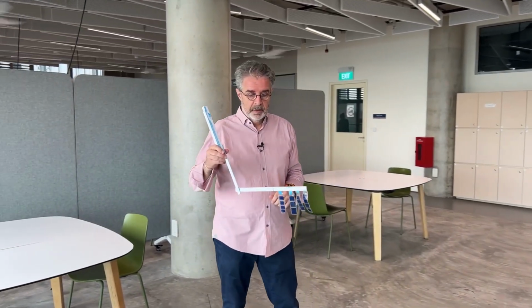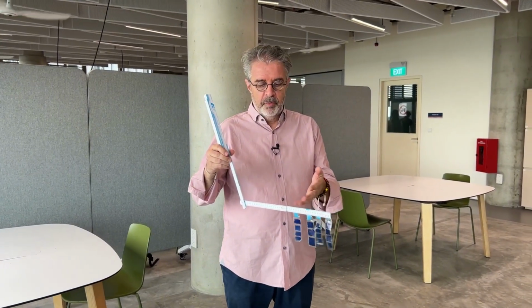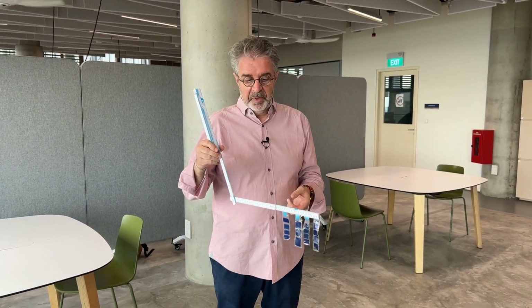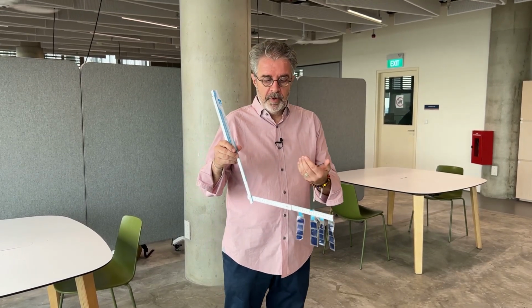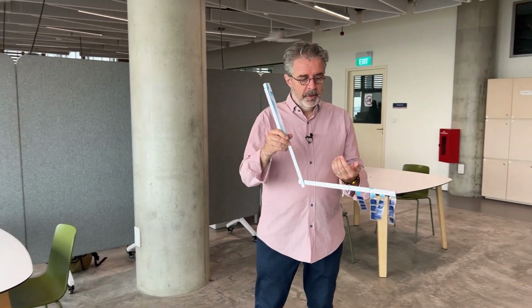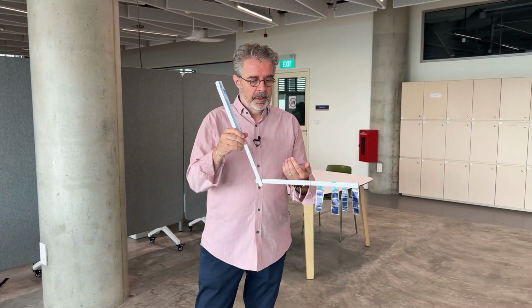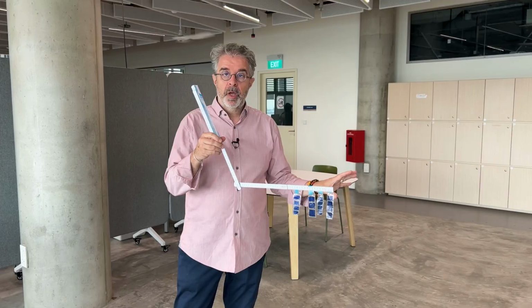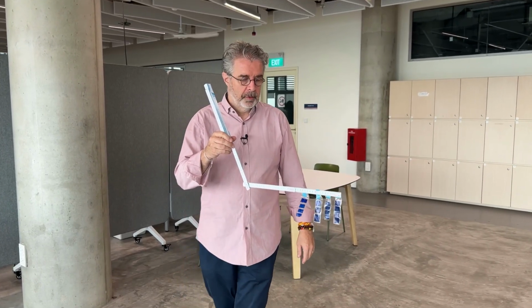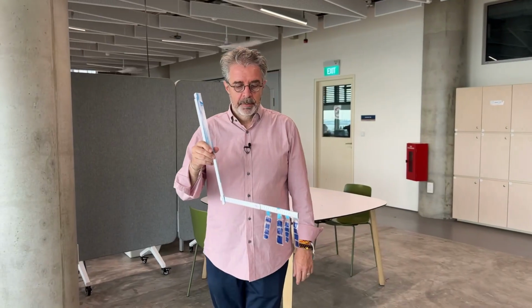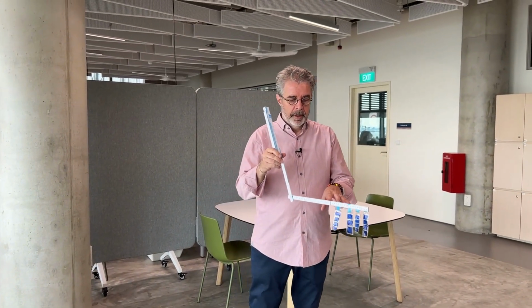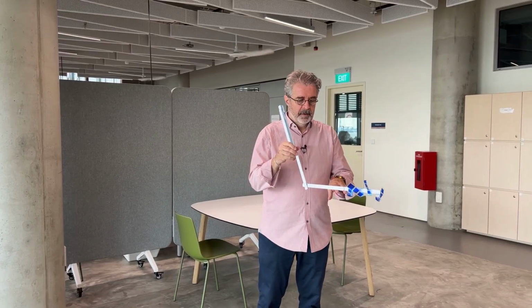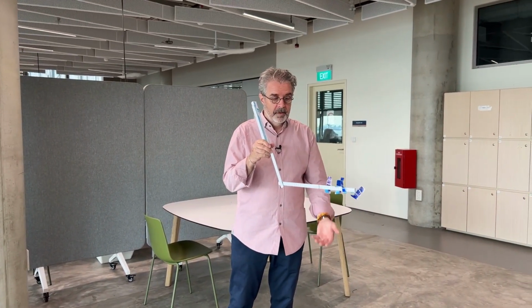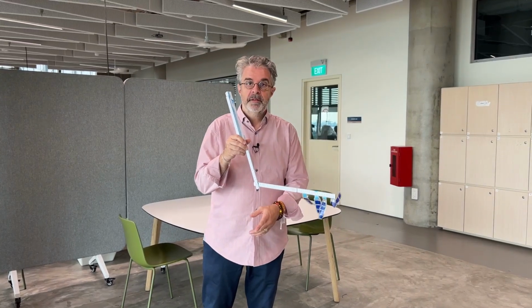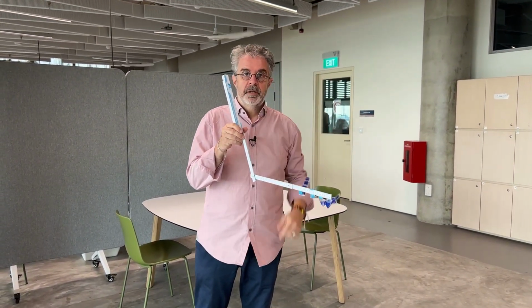Let me first go under the fan. What the device shows is a strong air movement under the fan, probably something like 2 meters per second. Now I move out of that fan zone, just 0.5 meter, and we are in the still air zone—there's no air movement here. Let me move further, into the very center between the two fans, and look at my little device. It indicates an uplift in the very center, the air colliding between the two fans, lifting up and moving through that space.